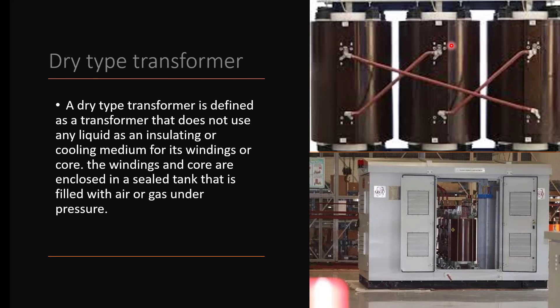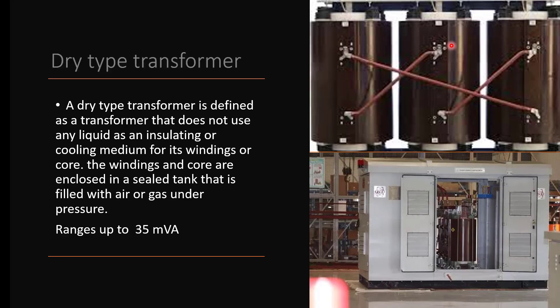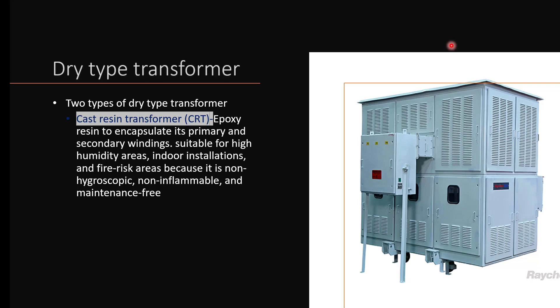The first type is the dry type transformer. As the name suggests, it does not use any oil or liquid for cooling or insulation. The windings are enclosed in a sealed tank filled with air or gas under pressure. If the transformer is located inside a building, a dry type transformer is used. It is rated up to 35 MVA. Within dry type transformers, there are two types. The first is the cast resin transformer, which is very commonly used. Epoxy resin is used between the primary and secondary winding as an insulating medium. It can be used in high humidity areas, indoor installations, and fire risk areas because it is non-hygroscopic, non-inflammable, and maintenance-free.